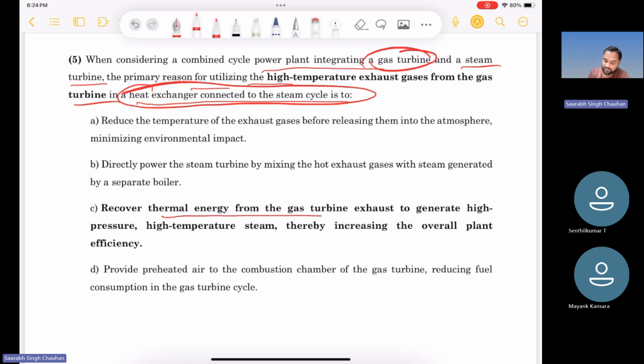Recover the thermal energy from the gas turbine exhaust to generate high pressure, high temperature steam, thereby increasing the overall plant efficiency. As we have discussed earlier, and probably will discuss in upcoming sessions, if the average temperature of heat addition is increased, efficiency will increase, and if the average temperature of heat rejection is decreased, efficiency will increase.